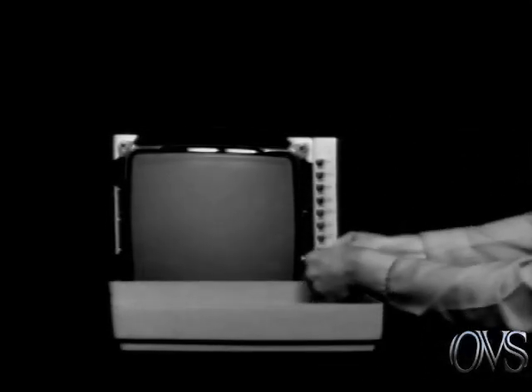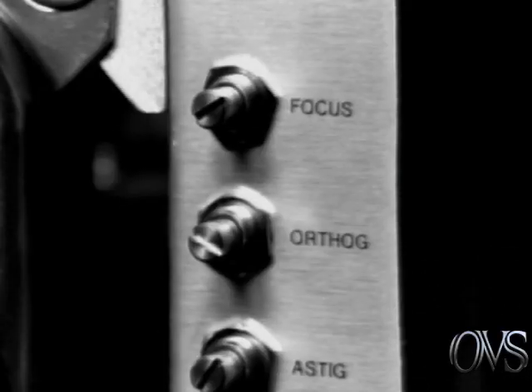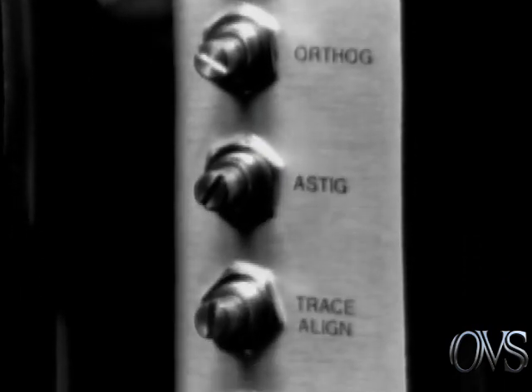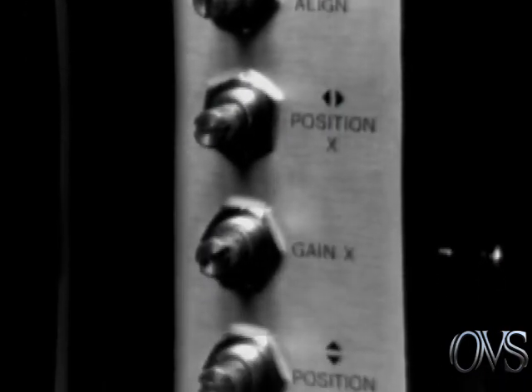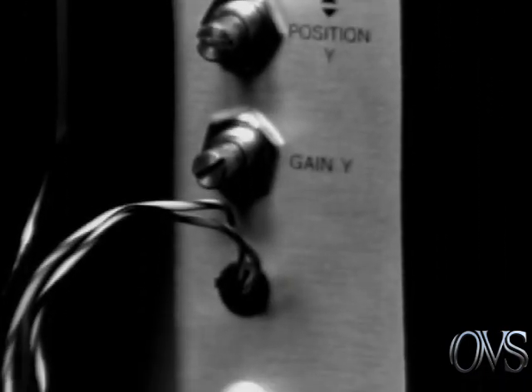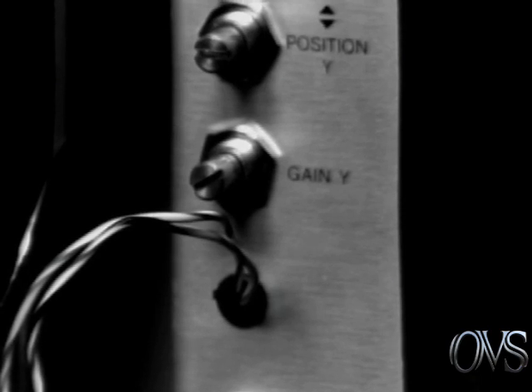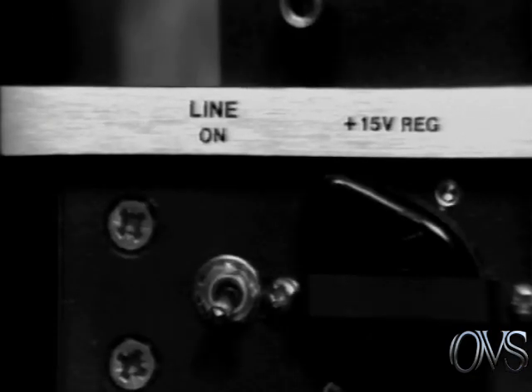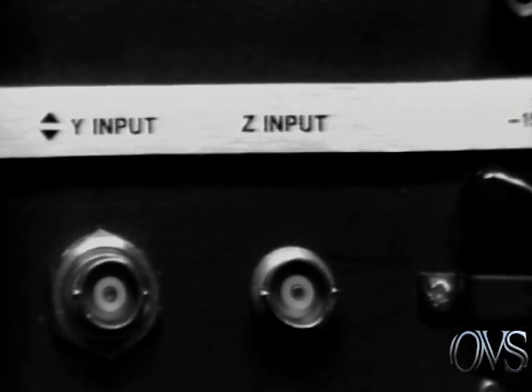By loosening two screws, removing the intensity knob, and disconnecting the quick disconnect plug for the power on indicator, the plastic mask can be removed. This exposes other controls used less frequently: orthogonality, trace align, gain X, and gain Y. On the rear panel are the power on switch, line input and voltage selector, and X, Y, and Z axis signal input connectors.